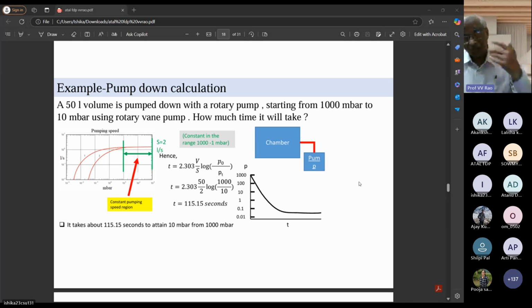You cannot get that. You have to read again and again. Then only you get a feel of all these things. But right now, if 120 seconds is not happening, you should doubt whether the valve is opened at all.